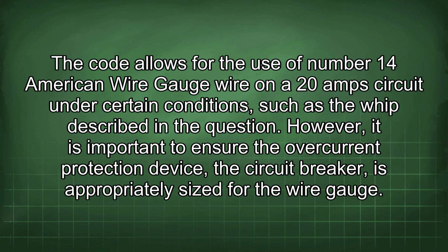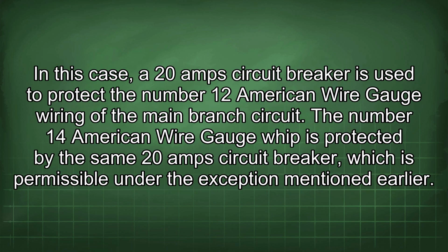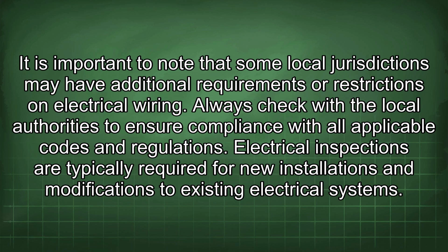However, it is important to ensure the overcurrent protection device, the circuit breaker, is appropriately sized for the wire gauge. In this case, a 20 amp circuit breaker is used to protect the number 12 American wire gauge wiring of the main branch circuit. The number 14 American wire gauge whip is protected by the same 20 amp circuit breaker, which is permissible under the exception mentioned earlier. It is important to note that some local jurisdictions may have additional requirements or restrictions on electrical wiring. Always check with the local authorities to ensure compliance with all applicable codes and regulations.